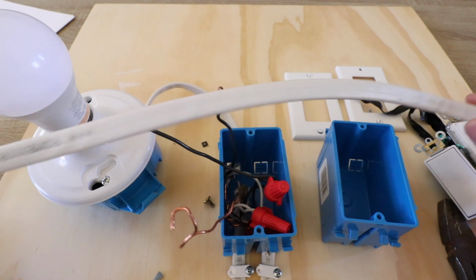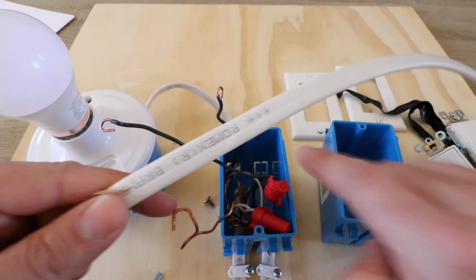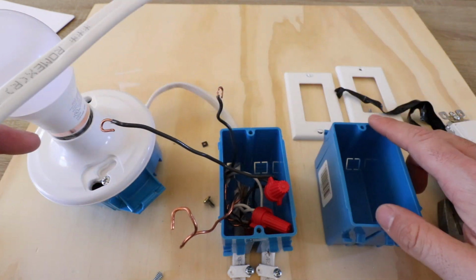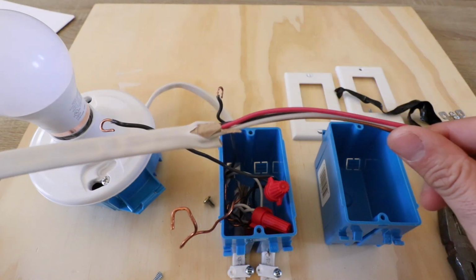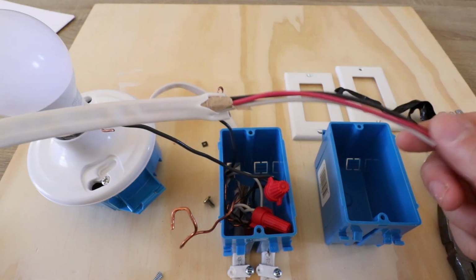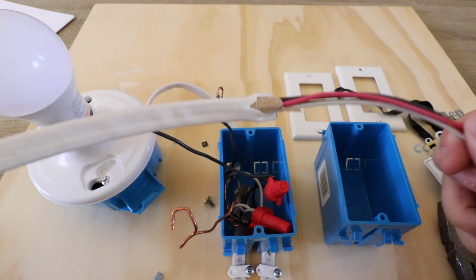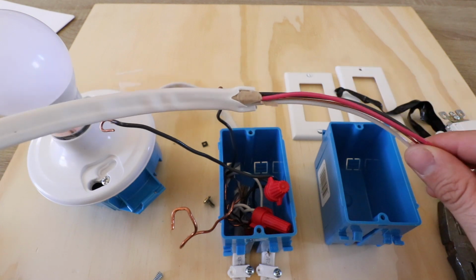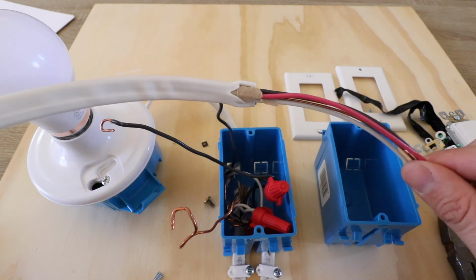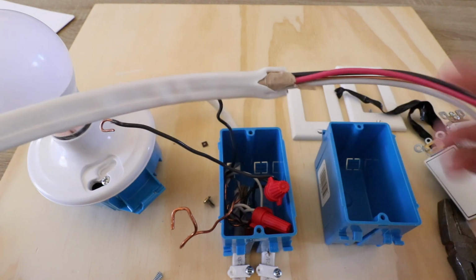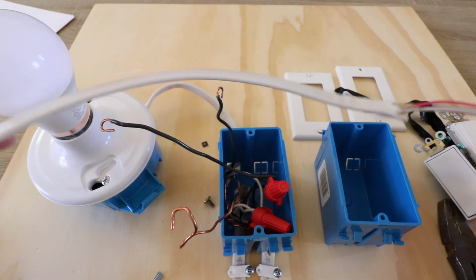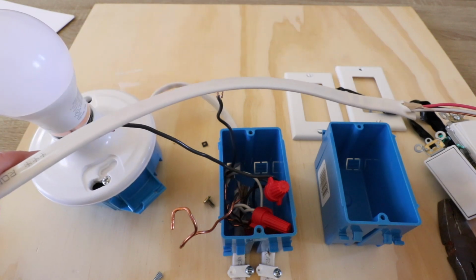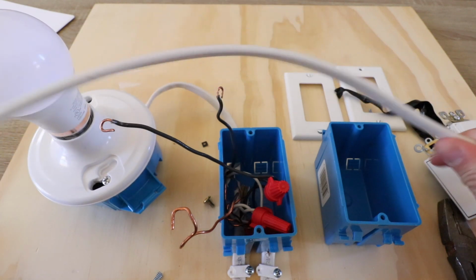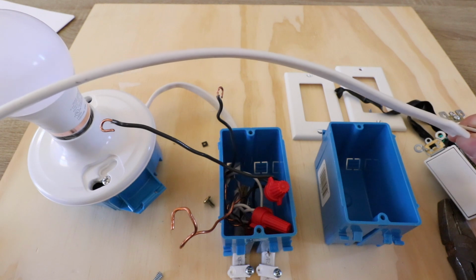Now you would take your wire and run it from this box to this box. I've already got it stripped, but typically you don't want to do that while pulling wire, because it will get snagged on things behind your walls if you're pulling it through a wall. If you've got drywall open, it's no big deal, pretty easy to run the wire. But typically it's much easier to pull the wire if it hasn't been stripped.